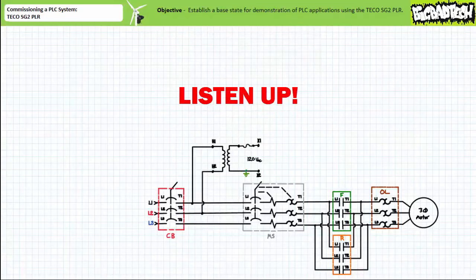It should be stated that the TECO SG2 PLR must not contain an active program in memory before continuing with the installation. If an inadvertent program remains in memory, upon power up, the device will immediately execute that program with potentially disastrous consequences. Take the time to ensure your device is cleared and stopped before you get yourself into trouble that you cannot get out of.